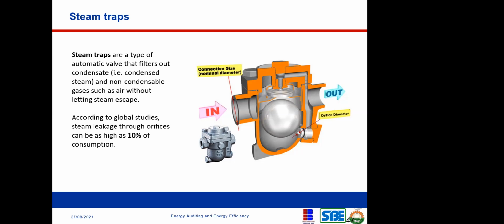So when it fails to close, what happens? It remains open, and then steam that should go for the production process will now begin to go out and begin to waste. Mind you, this steam trap is an enclosed system. You're not seeing it. Inside it, you have all the mechanisms that enable it to open, allow water to go out, and then close back. But sometimes it might just open and then fail to close. The steam will just keep going out through that process.